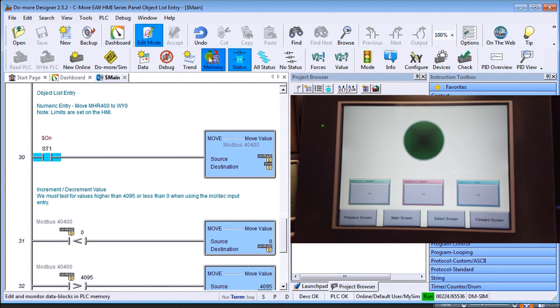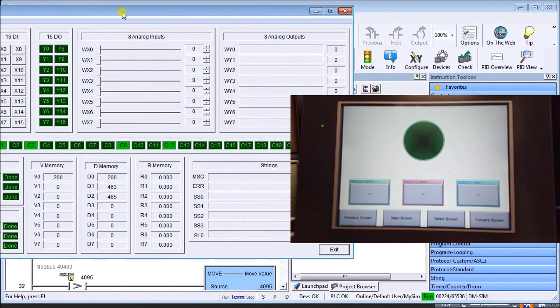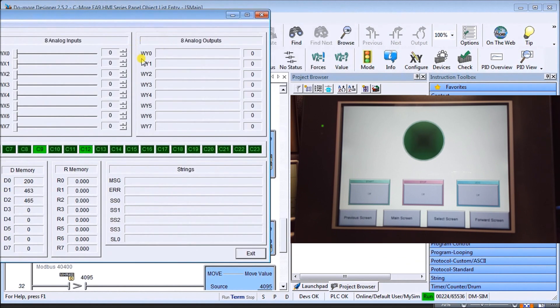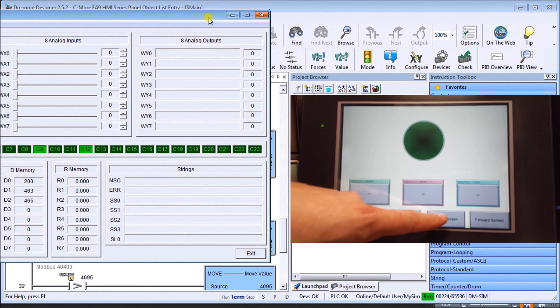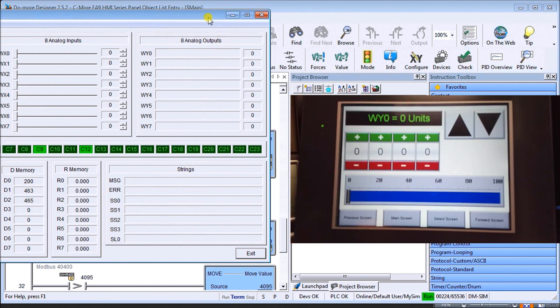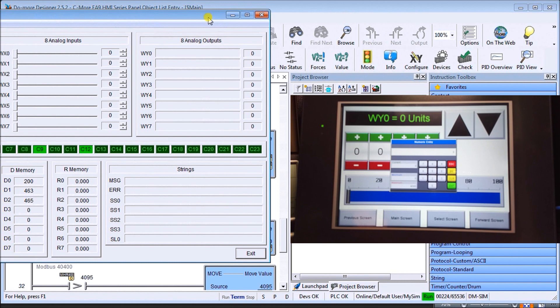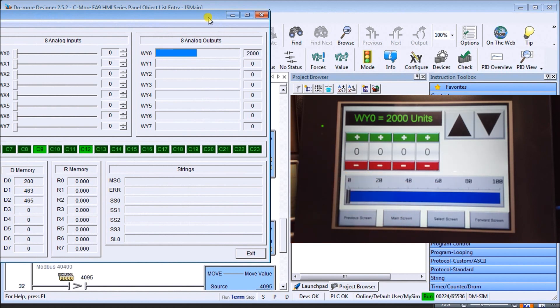Here is our object list entry on the actual HMI. For our numeric entry we've transferred MHR 400 into WY0, so anything that happens in that register will be transferred. Bringing up the simulator — WY0 is located here and goes from 0 to 4095. Going to our screen and selecting object entry it looks exactly like our simulation. Choosing numeric entry, we'll put in 2000, hit enter, and 2000 appears — also appearing under WY0 as expected.